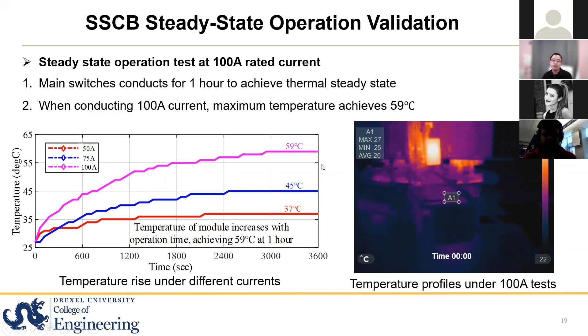After all, we also tried to measure the efficiency based on the voltage drop we measured. We can see at the very beginning we have higher efficiency, above 99.96%. Since we have the heat up of the power module, and we know the internal resistance increases with temperature and time, you can see that as time goes on, our efficiency goes down a little bit, but after 1 hour it stabilizes at about 99.958%... [efficiency figure as measured].